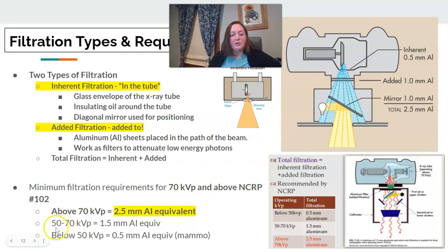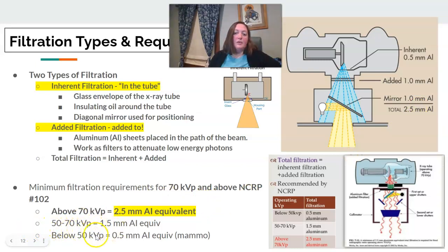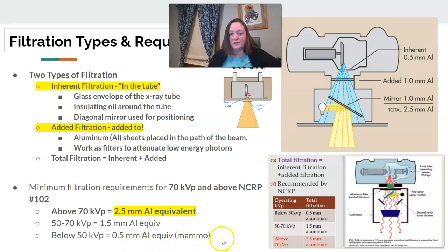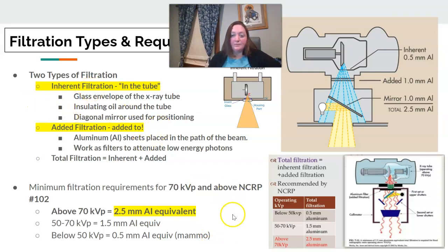If it's below 70 KVP, there are specific settings, and below 50 KVP — which we'd see in mammography — there are specific requirements as well, though that's not mainly seen in diagnostic imaging. To calculate total filtration, you simply add the two together: inherent plus added.